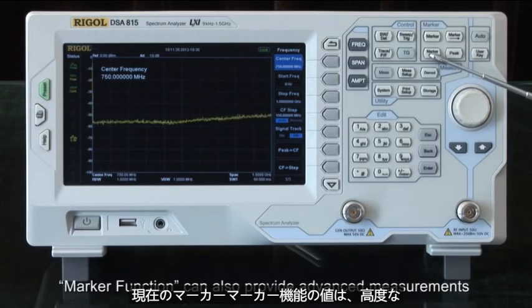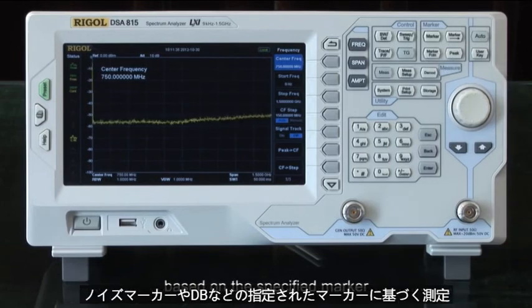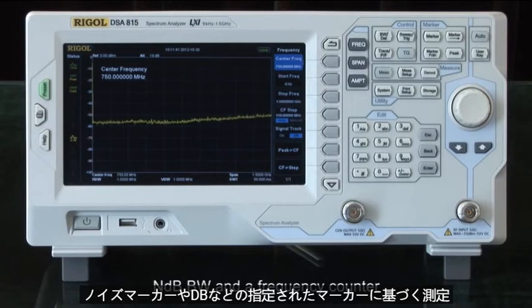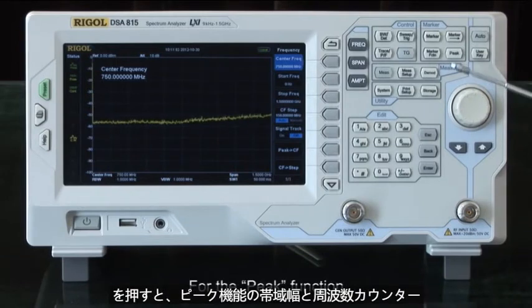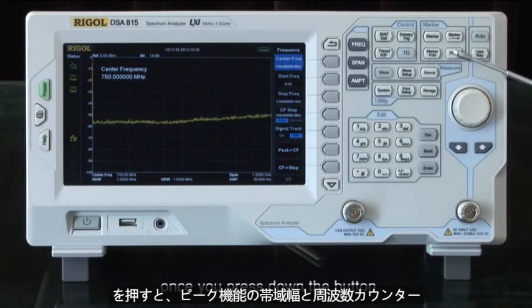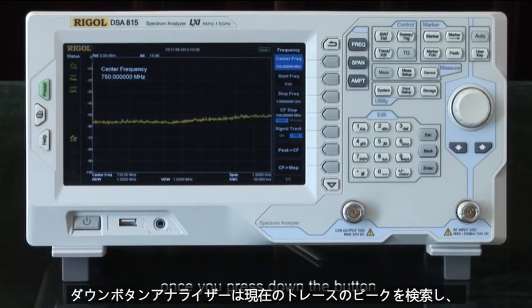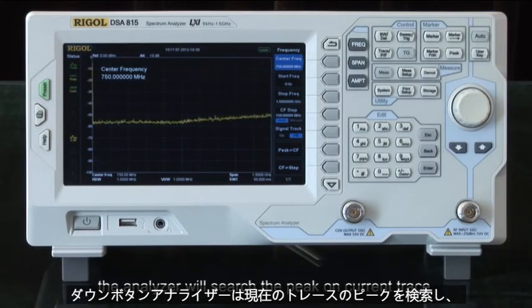The marker function can also provide advanced measurements based on the specified marker, such as noise marker, dB bandwidth, and a frequency counter. For the peak function, once you press the down button the analyzer will search for the peak on the current trace and open the search parameter menu.